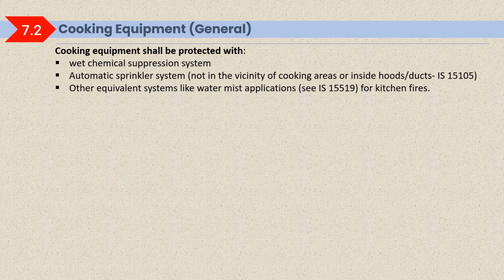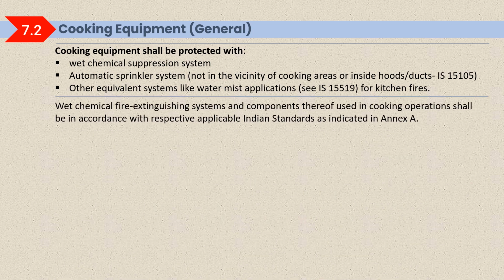So we need to provide a sprinkler or smoke detector system for other parts apart from the duct, hood and filter. So other equipment will protect if fire propagates from the kitchen to the other part of the area. Cooking equipment shall be protected with a wet chemical suppression system, or an automatic sprinkler system not in the vicinity of the cooking area or inside the hood, or other equivalent systems like water mist application for kitchen fire. So a sprinkler system is not recommended in the vicinity of the cooking area.